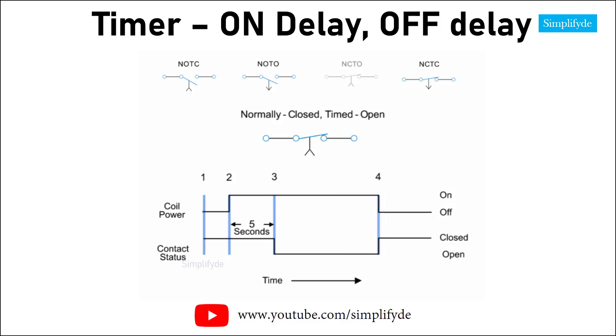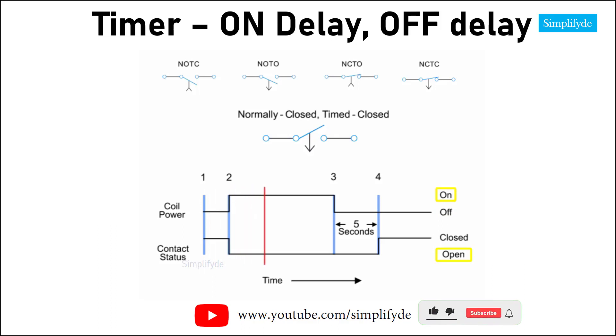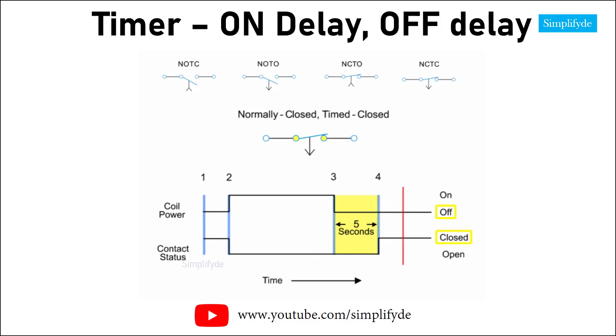The last time delay relay we will look at employs a normally closed timed closed (NCTC) contact. Similar to the NCTO contact, this type of contact is normally closed when the coil is de-energized, and opened by the application of power to the relay coil. However, unlike the NCTO contact, the timing action occurs when the coil is de-energized instead of when it is energized. Thus, the contacts open immediately when the coil is energized, and close five seconds after the coil is de-energized.